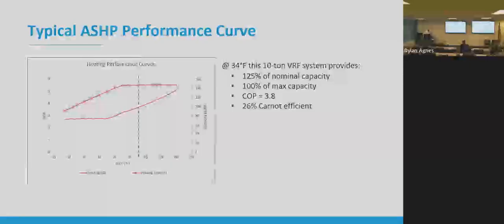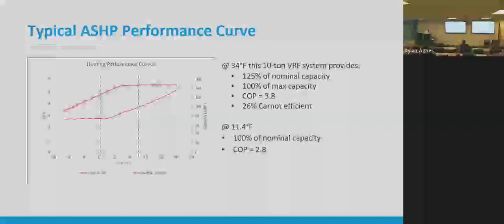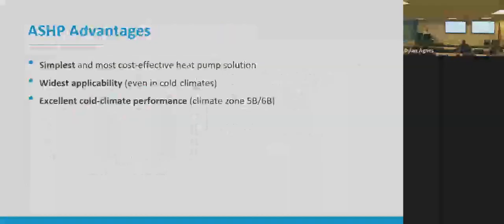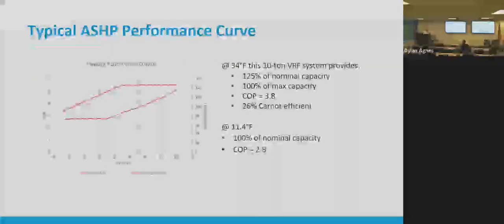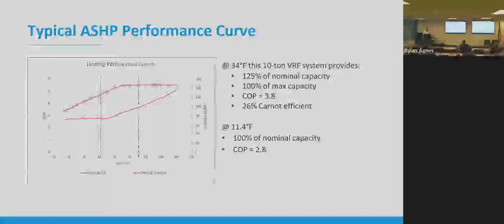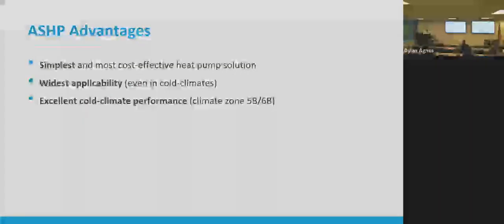Probably some room to grow there, but all that to say is a lot of performance at a lot of the year. And even when you go down to design, it's still 100% of nominal capacity. It's still delivering 10 tons, 120 MBH capacity with a COP of almost 3. And again, that's not a cold climate unit. That's just kind of off the shelf. And it can also go down to -15, which is, I think, a 50-year max here. So still delivering constant heat down to -15. I'll speak a little bit more about real cold climate units later.